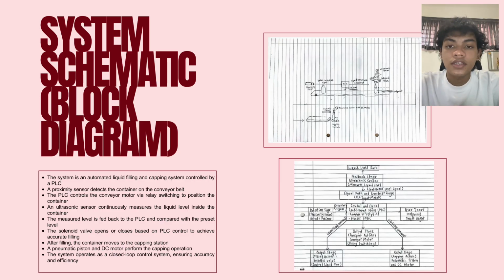Second, feedback and signal conditioning. As the liquid enters, the ultrasonic sensor continuously measures the level. This data is fed back through the PLC input module. The third one, control logic. The PLC acts as a brain, comparing the real-time sensor data against the user-defined set point. The last one is output action. Based on this comparison, the PLC controls the solenoid valve to achieve an accurate fill.